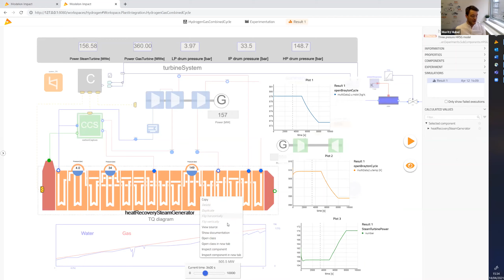The reason is quite similar to the first demo: water has a much higher heat capacity than carbon dioxide. So even though the flue gas temperature and mass flow decrease, we actually have more power available in the heat recovery steam generator.